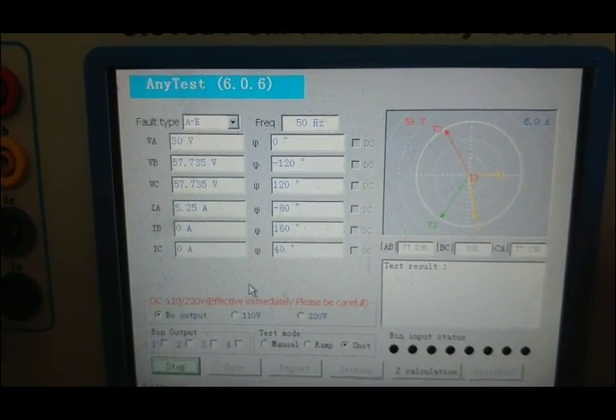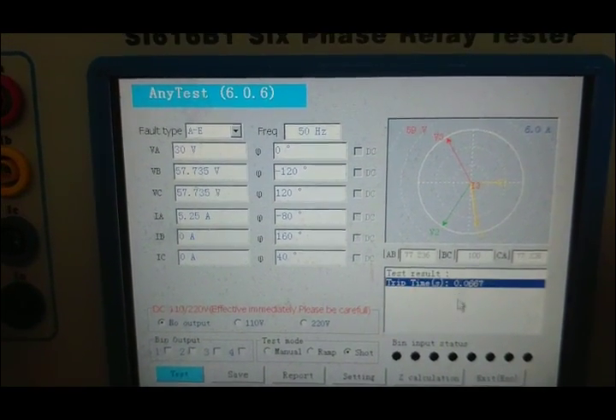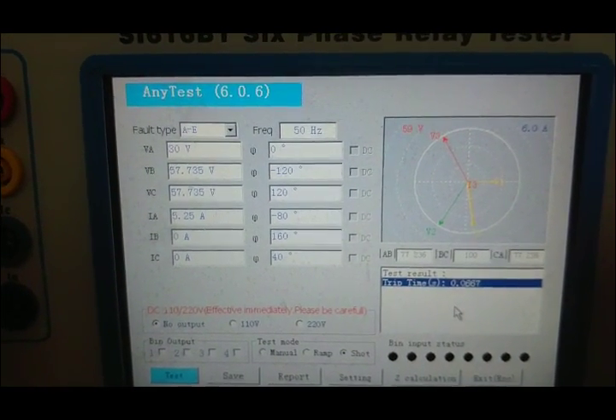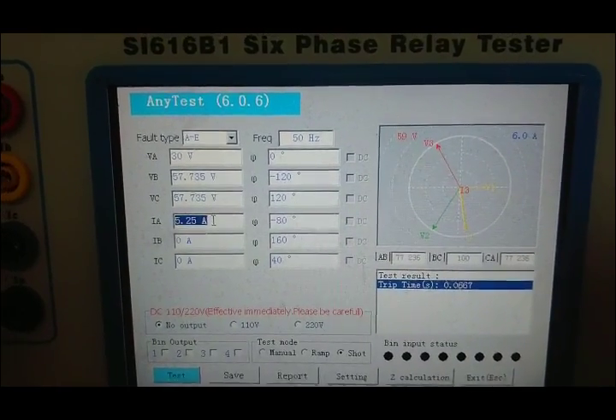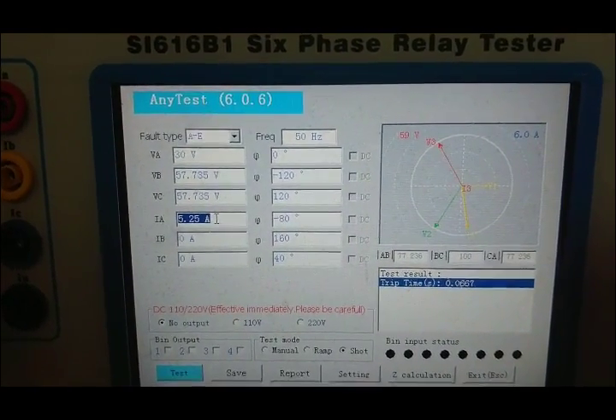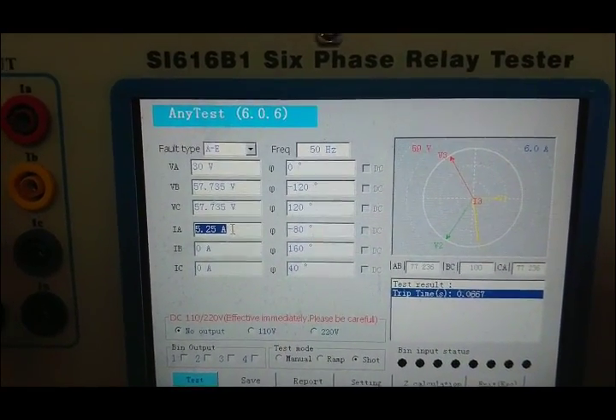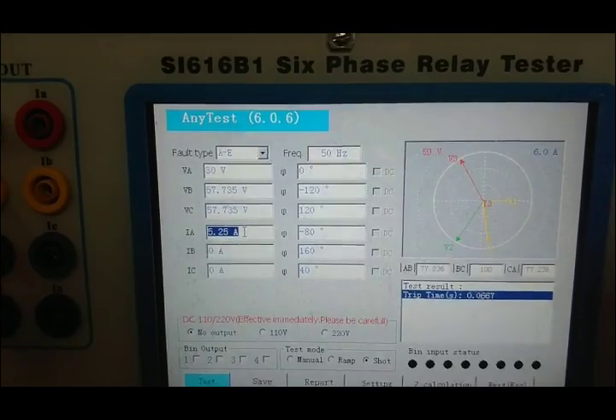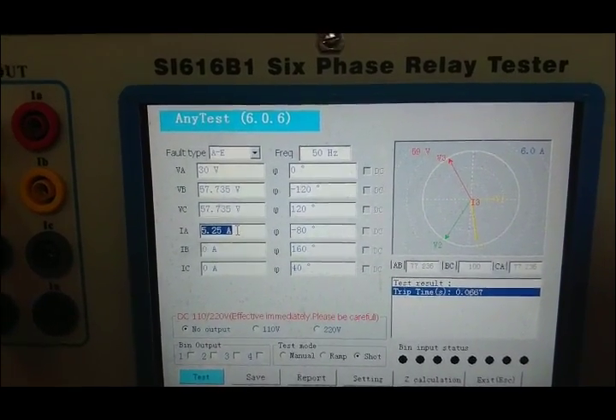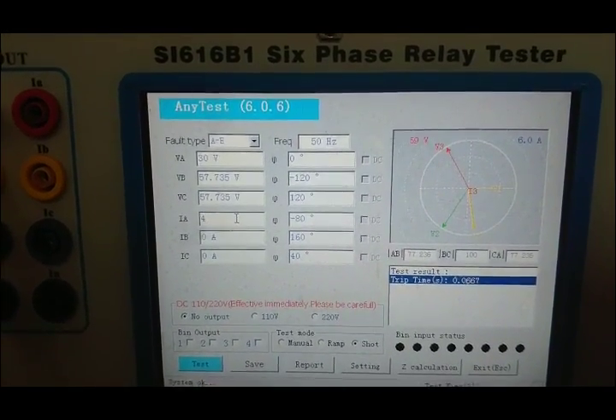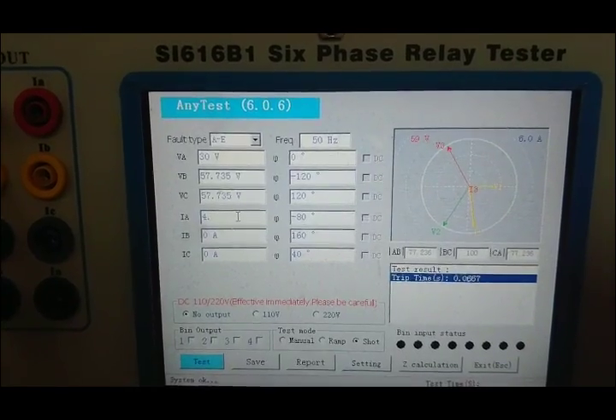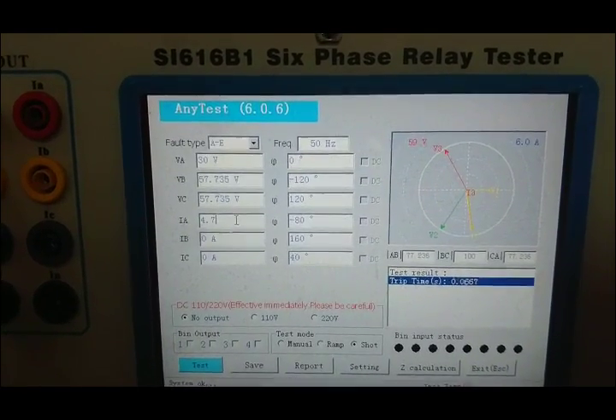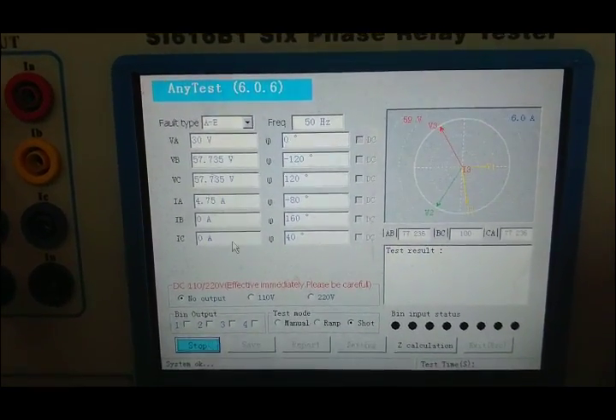We can see the test result is 0.0667 seconds. Next, we are going to verify 0.95 times the setting current value at 4.75 ampere.